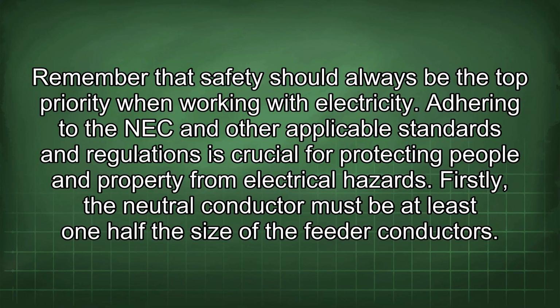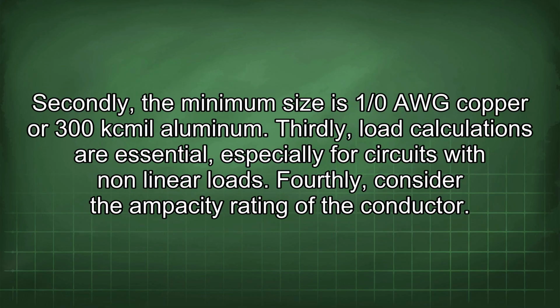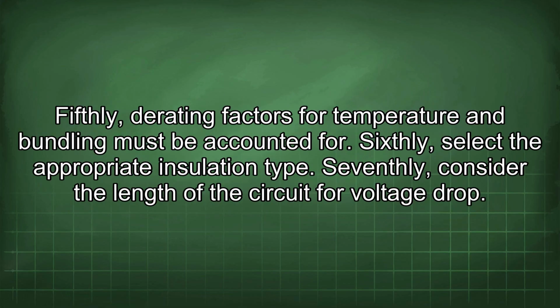Firstly, the neutral conductor must be at least 1/2 the size of the feeder conductors. Secondly, the minimum size is 1/0 AWG copper or 300 kcmil aluminum. Thirdly, load calculations are essential, especially for circuits with nonlinear loads. Fourthly, consider the ampacity rating of the conductor. Fifthly, derating factors for temperature and bundling must be accounted for. Sixthly, select the appropriate insulation type. Seventhly, consider the length of the circuit for voltage drop.